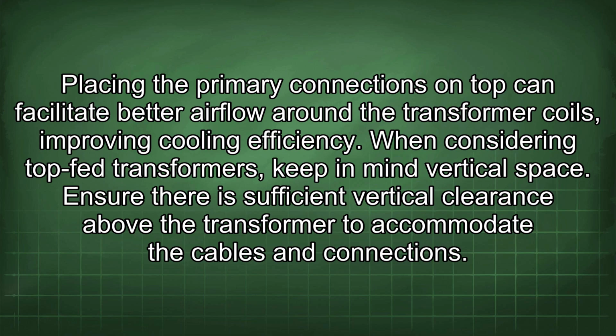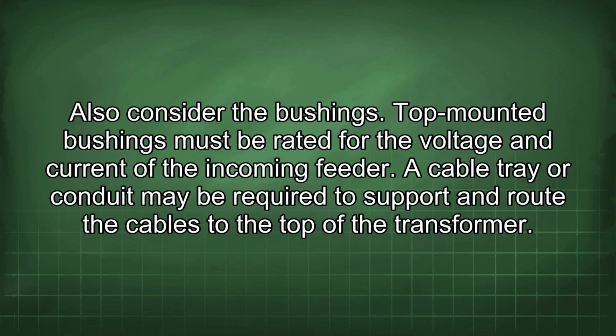When considering top-fed transformers, keep in mind vertical space. Ensure there is sufficient vertical clearance above the transformer to accommodate the cables and connections. Also consider the bushings. Top-mounted bushings must be rated for the voltage and current of the incoming feeder. A cable tray or conduit may be required to support and route the cables to the top of the transformer.